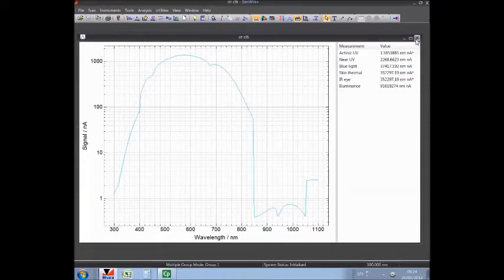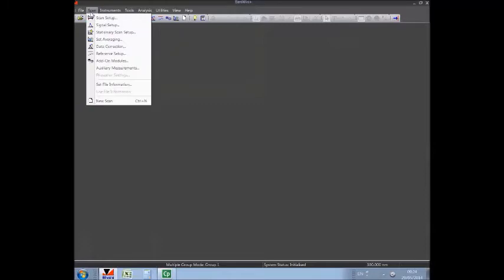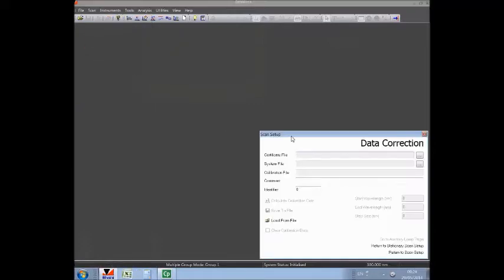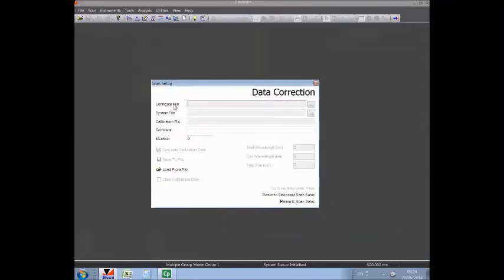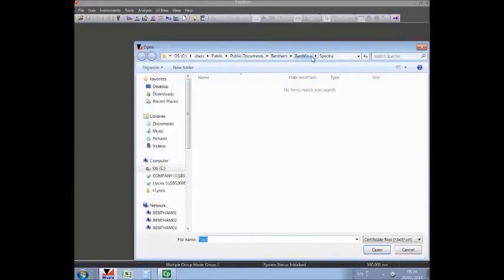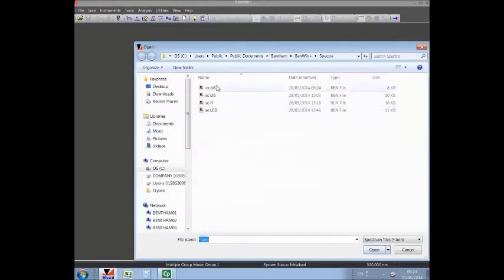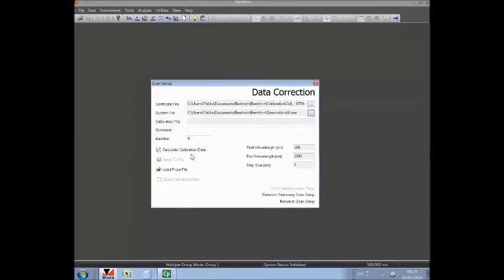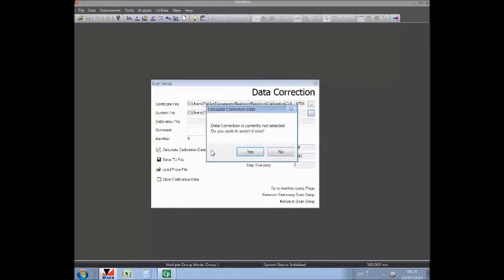Now, if the measurement region of 300 to 1100 nanometers only is required, we can directly apply data correction. We go to scan, data correction. The certificate file is the true calibrated irradiance file of the CL6, which is in the BenWin Plus calibration folder, CL6. The system file is the average we just saved, the irradiance of the CL6, and we can hit calculate calibration data.